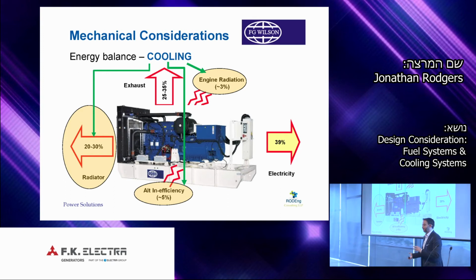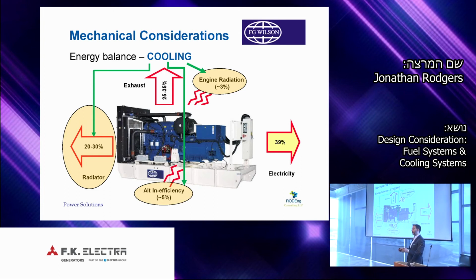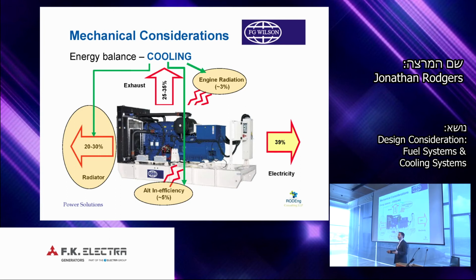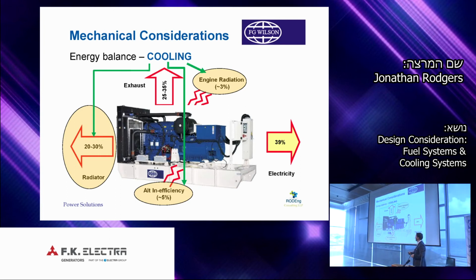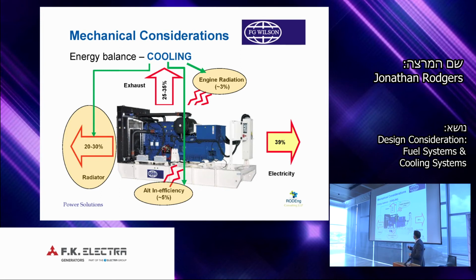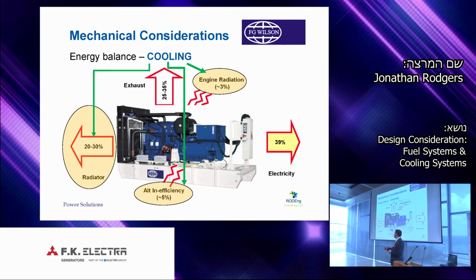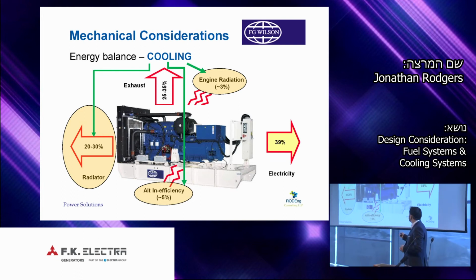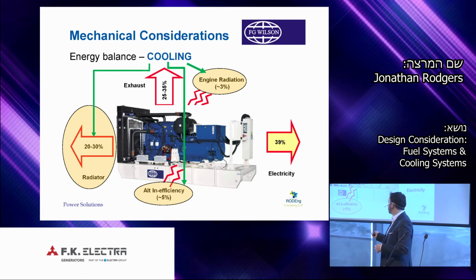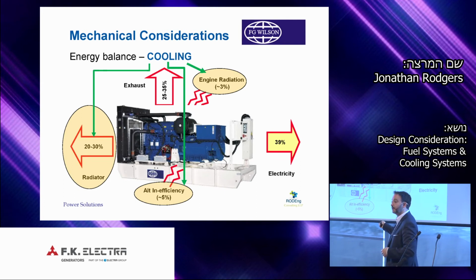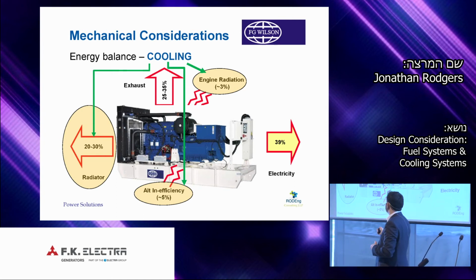Now we want to look at the major source of energy that's dissipated and how we control the heat from the engine, engine cooling. So when we think of engine cooling, we think about the radiator mounted on the front of the engine, but we also need to look at the heat that is radiated off the engine block and any heat that comes from the windings of the alternator. So typically an alternator will be 95 to 97% efficient. So the 5% inefficiency of the alternator will be heat given off from the windings and ejected through the outlet of the alternator. This heat needs to be considered because it will come onto the radiator and onto the cooling system. So the cooling system needs to deal with that.